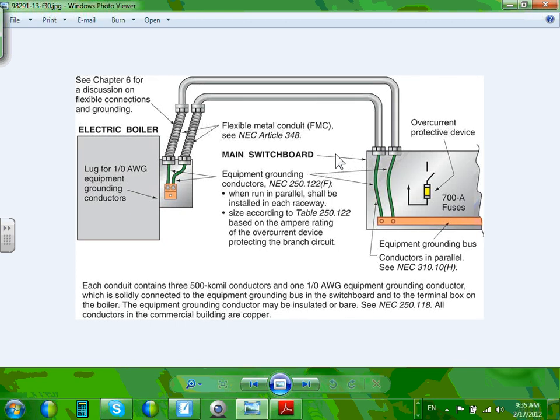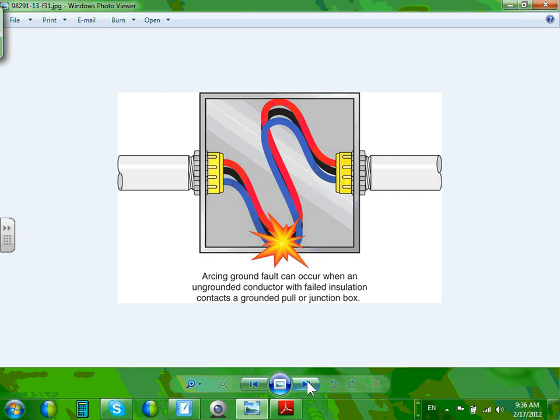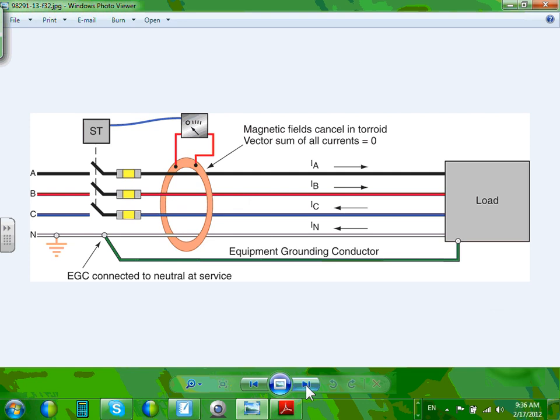The equipment grounding conductor, guys. If you have a conduit like this one with a flex at the end, right? You have to pull an equipment grounding conductor because the flex is not rated as an equipment grounding conductor. So you have to pull one in the flex on that one. This is just to tell you why we ground things, because you don't want to arc and spark and so forth. GFCI protection, we talked about GFCI, guys, looks at the current in, the current out.